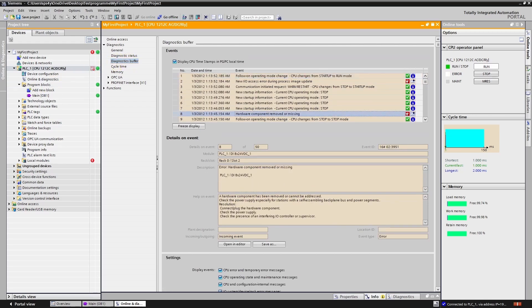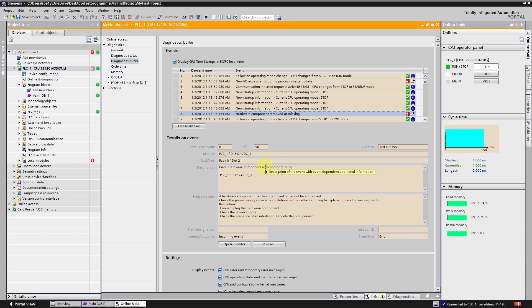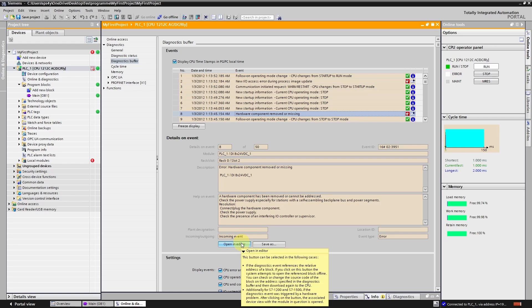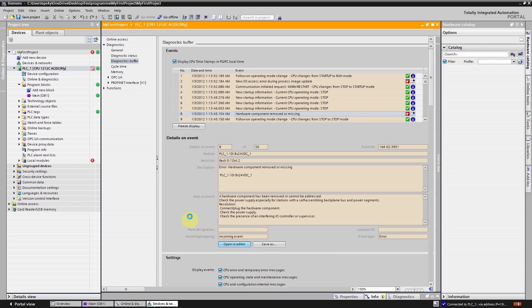In the diagnostic buffer you will find a plain text error description. It seems that the configured hardware module is missing. Below the description you will see a suggestion on how to resolve the issue. By clicking on open in editor you will be taken directly to the root of the error.